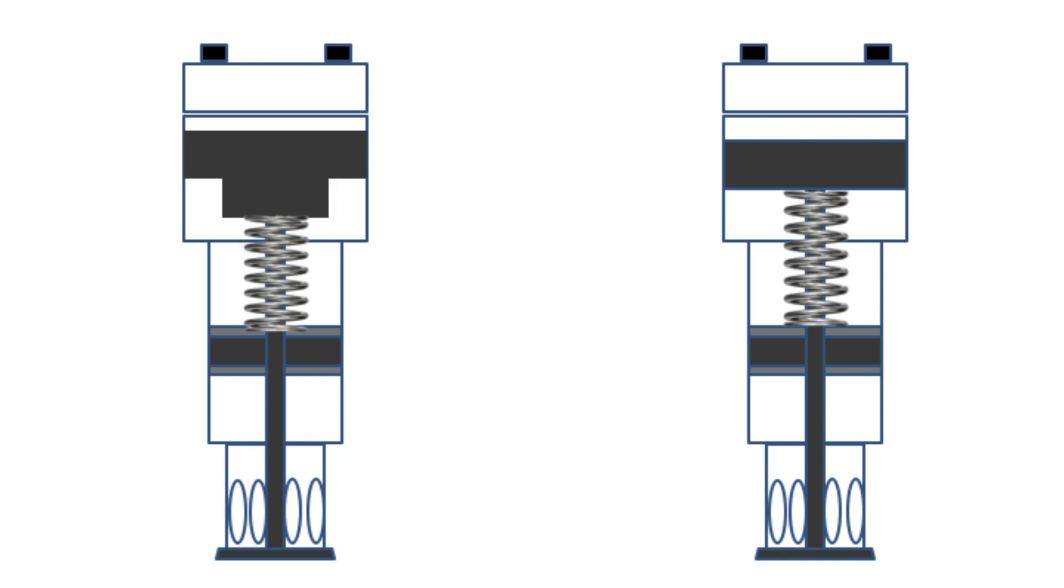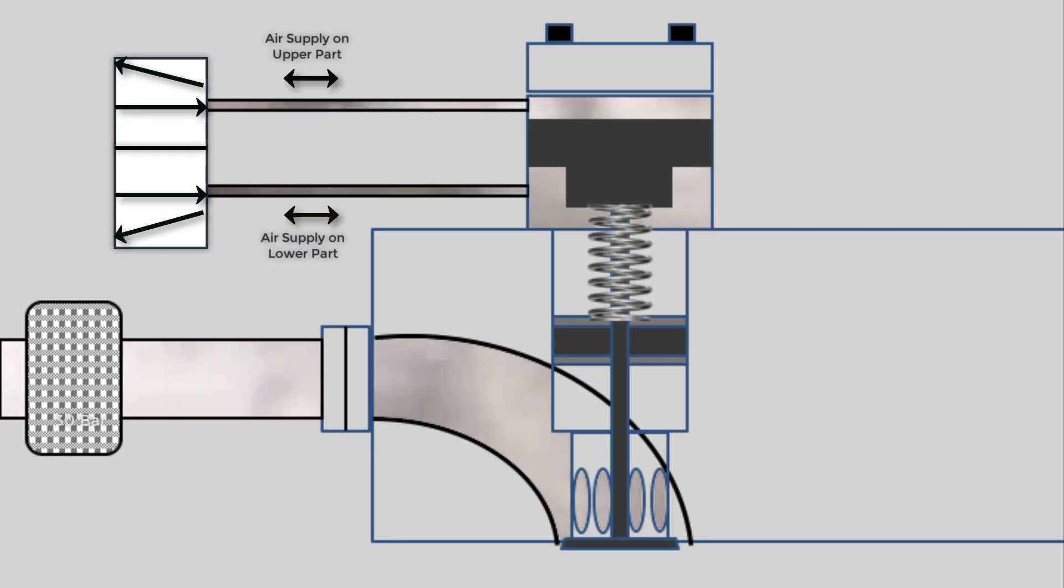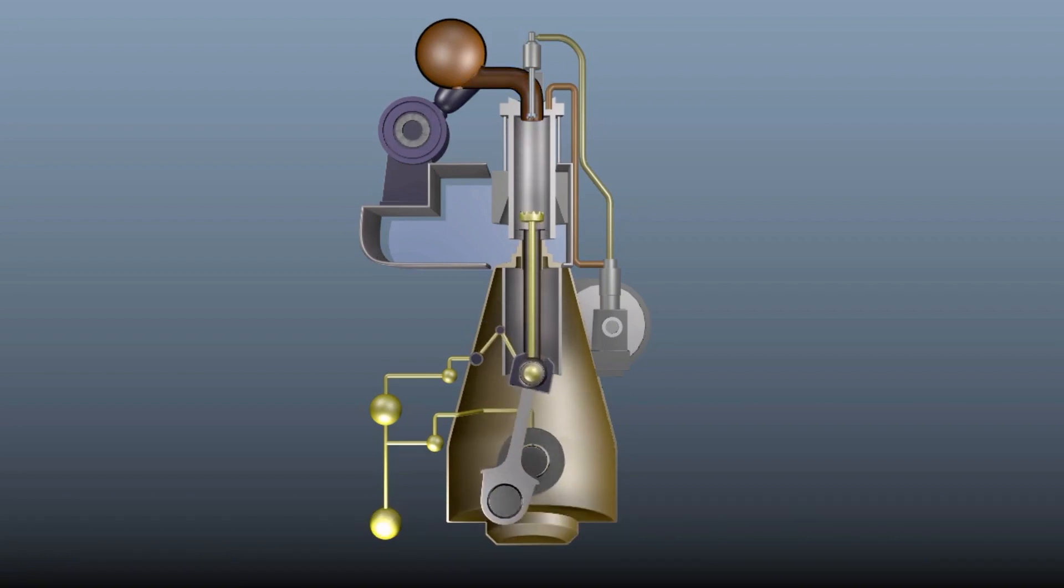In this type of air start valve, air on both sides of the operating piston is supplied via a control valve to maintain positive closing. This ensures the valve will remain closed even when the gas pressure is higher than the starting air pressure when the cylinder is firing.